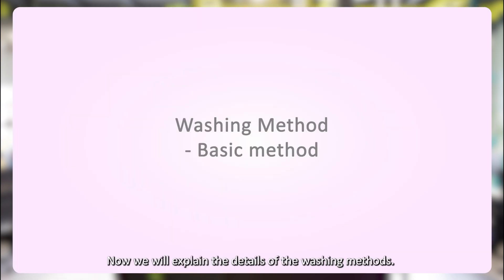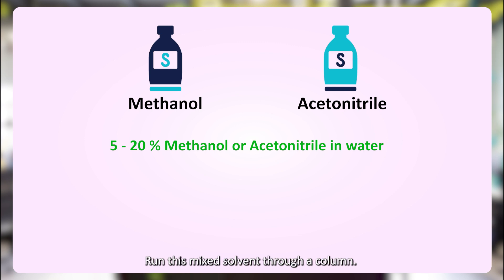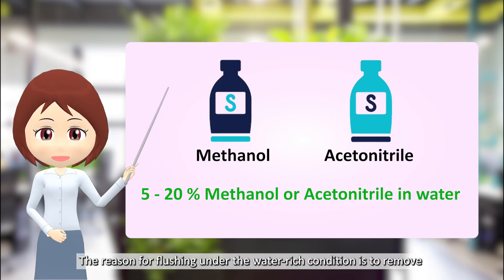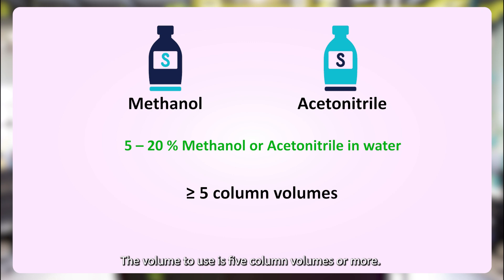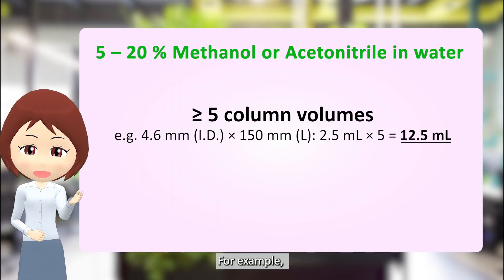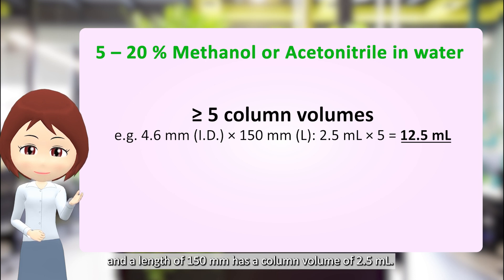Now we will explain the details of the washing methods. First, create a mixture of 5–20% methanol or acetonitrile and water, and run this mixed solvent through the column. The reason for flushing under a water-rich condition is to remove precipitated substances, such as salts remaining on the column. The volume to use is 5 column volumes or more. For example, a column with an inner diameter of 4.6 mm and a length of 150 mm has a column volume of 2.5 ml.